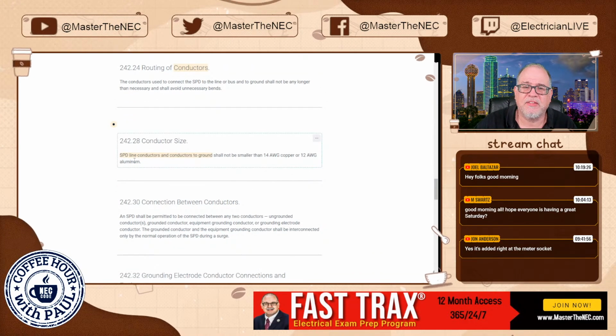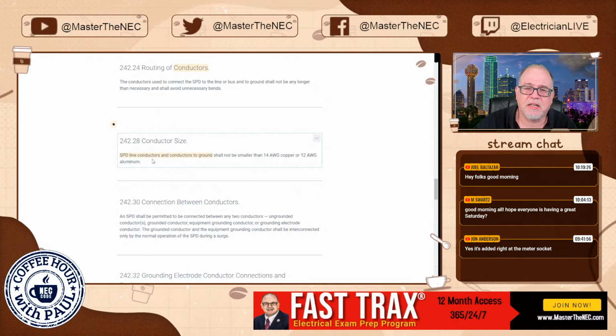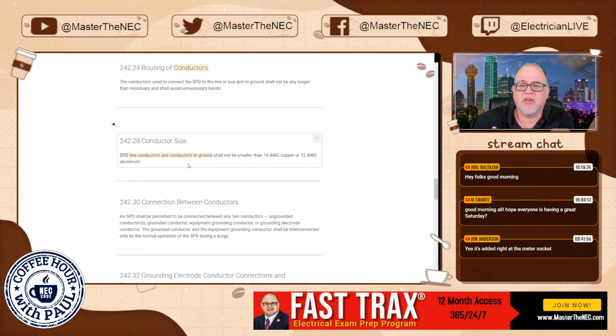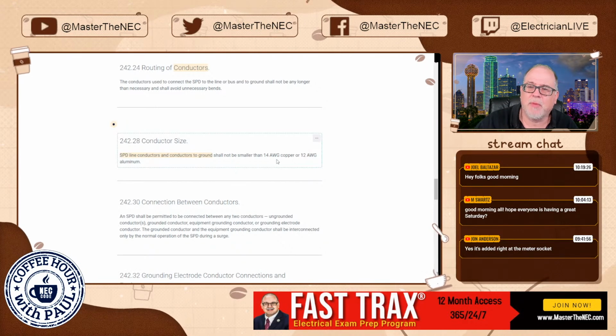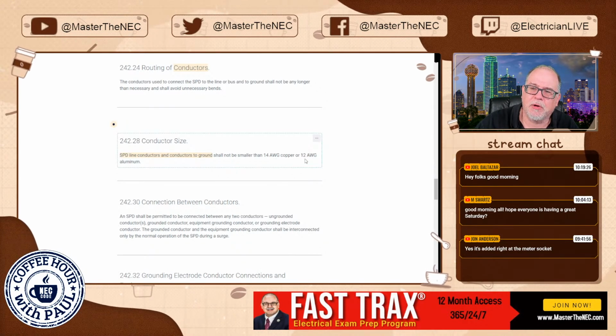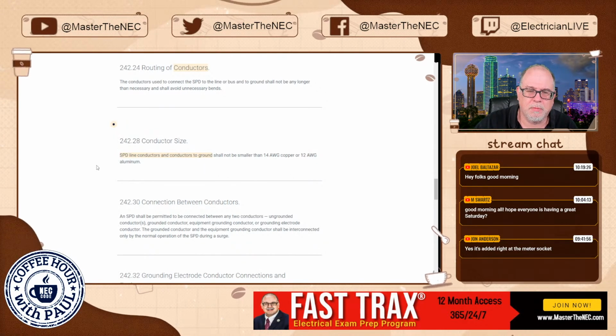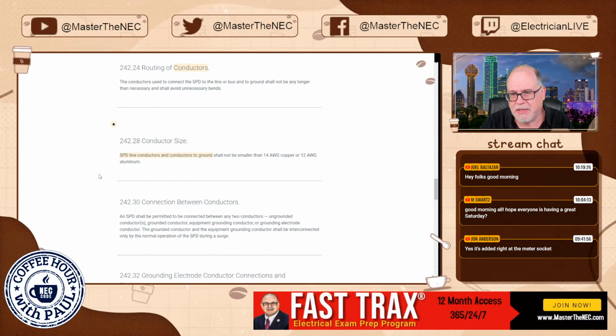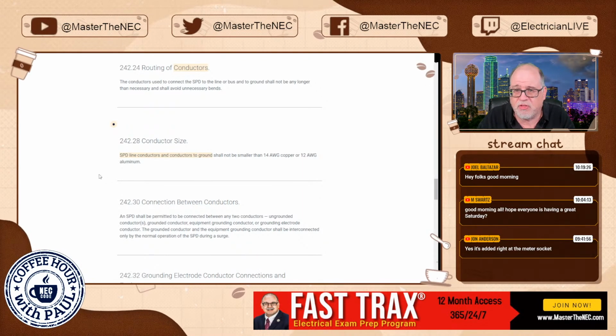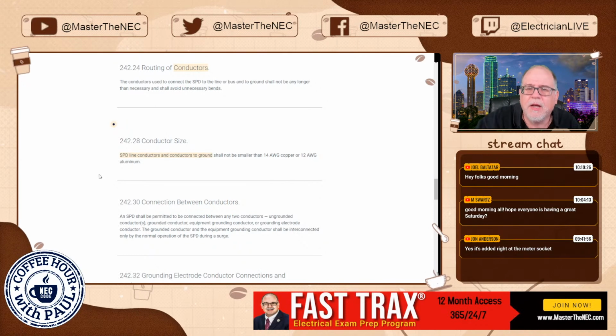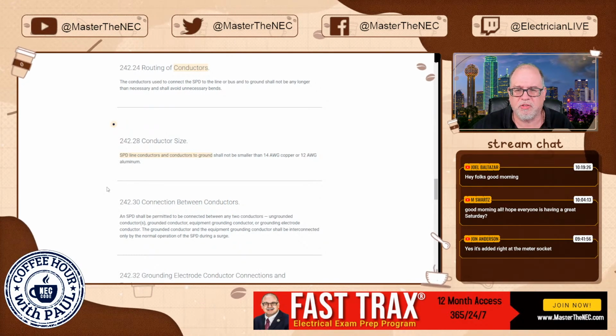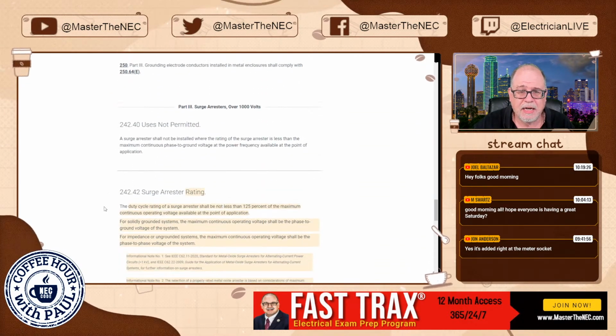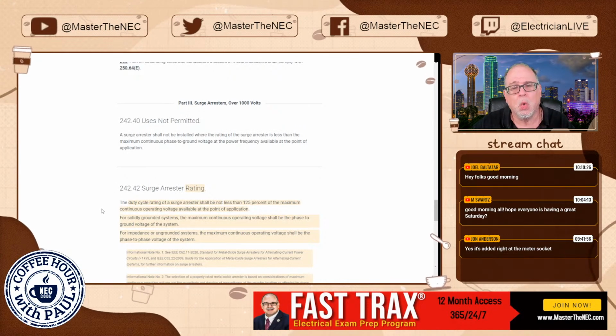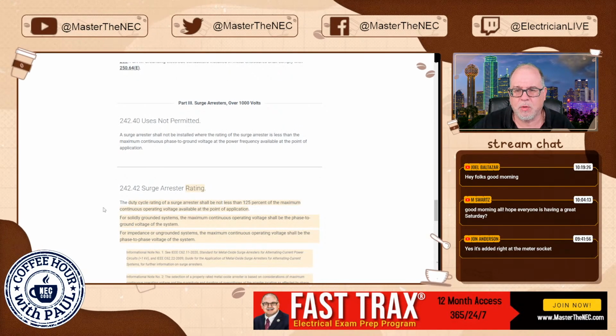242.28, conductor sizing. SPD line conductors and conductors to ground shall not be smaller than 14 AWG copper or 12 AWG aluminum. Again, you're going to look at the manufacturer's instructions anyway. This is telling you they just can't be smaller than that. Follow the manufacturer's instructions. Obviously, that's a no-brainer. They are going to come with the piece of equipment.